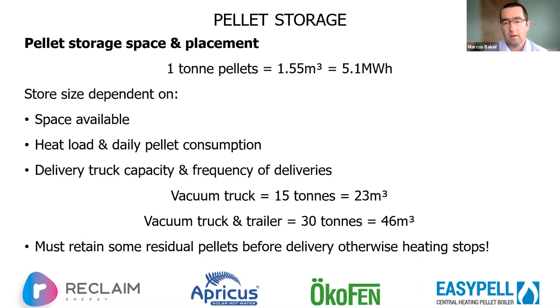Although there is sharing going on, and as the network of boilers out there increases, we're going to get more economies of network delivery, picking up a smaller amount each time, potentially dropping off, I should say. And obviously something that's a really important factor, there has to be some residual pellets. We can't take it right down to the wire, because no pellets, no heat, no domestic hot water. So we usually leave a residue of a ton or two in the bottom of the hopper before delivery happens.